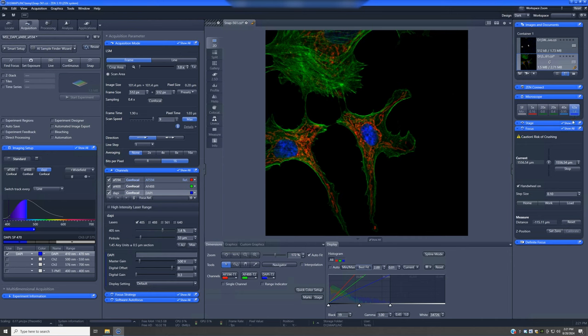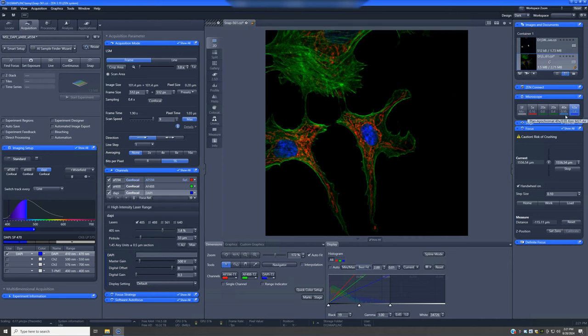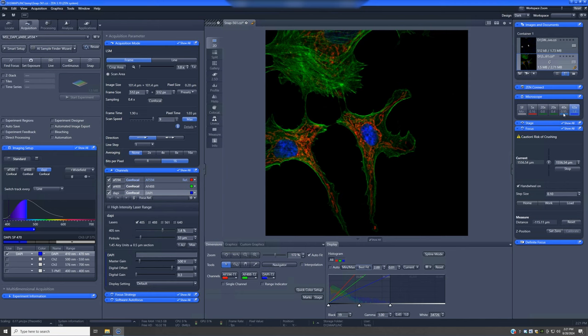If you have scenarios where the resolution provided by the 20x0.8 is not quite good enough, but you really don't need oil and you want to scan a large region where using oil might complicate things, we have this intermediate objective, which is a 40x0.95. This is an air objective with slightly higher resolution than the 20x0.8. It comes at a cost of a significantly reduced imaging area—it's four times smaller—and it is not as bright an objective as the 20x. But for certain circumstances, this 40x can be a good choice.